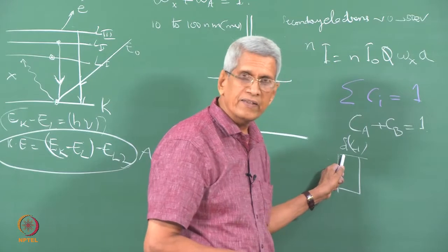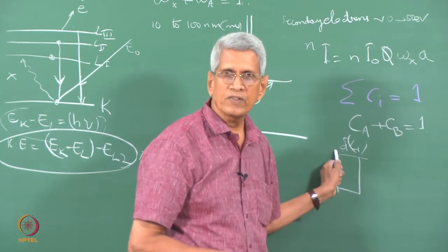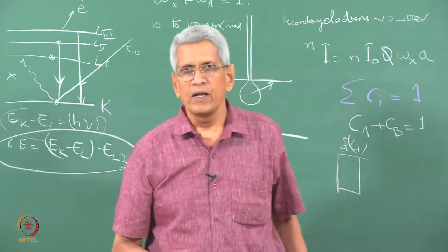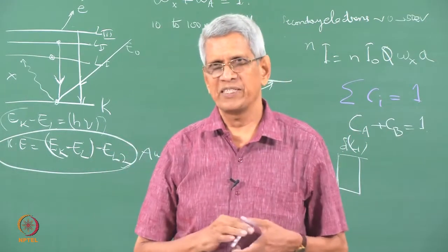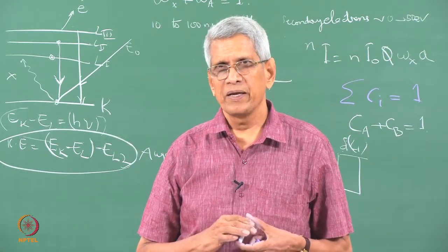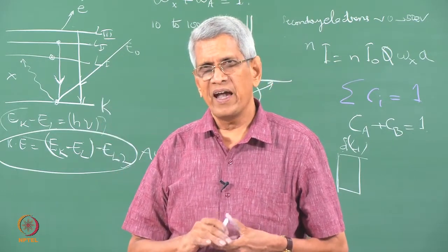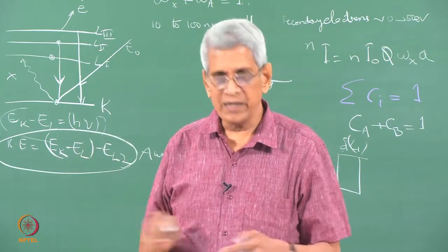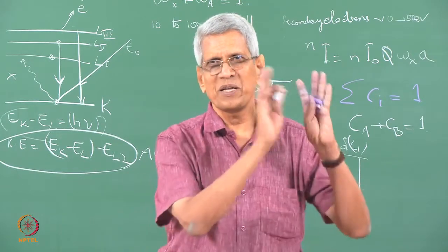In this layer, as the X-ray enters, it can cause a fluorescence here. So, if it causes a fluorescence here, that means that it ionizes the silicon K alpha. So, some part of the X-ray comes out, losing some specific energy. Okay. That means that a reduction in energy of the copper K alpha has occurred, and the copper K alpha energy minus this energy, corresponding to around 1.74 keV, at that position you get another peak.